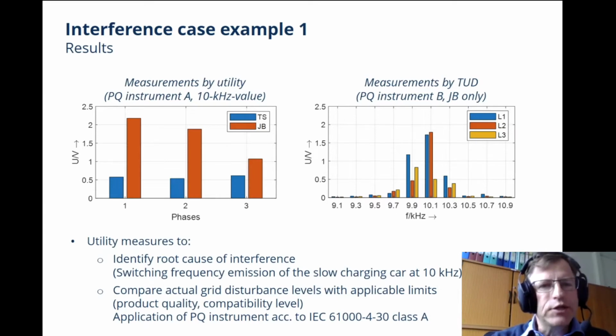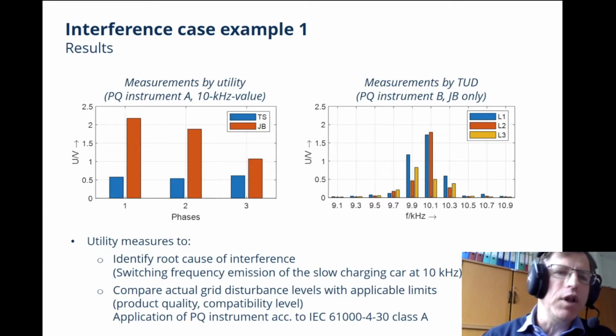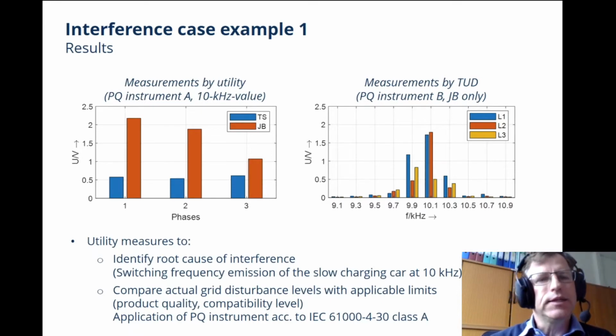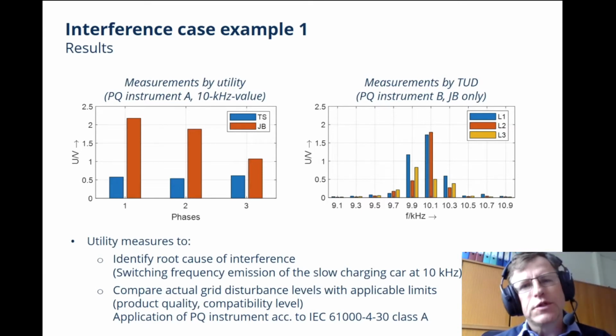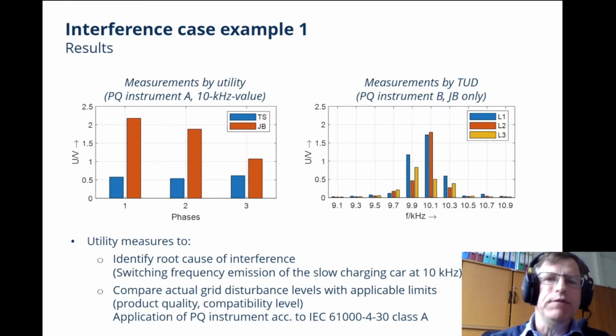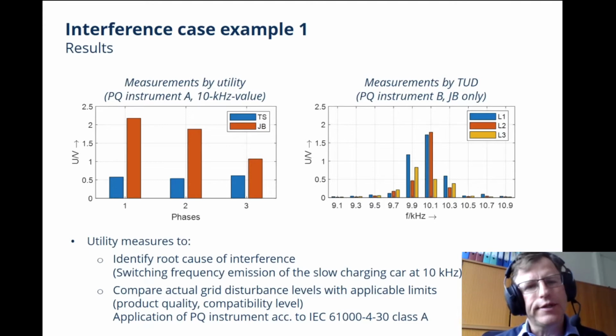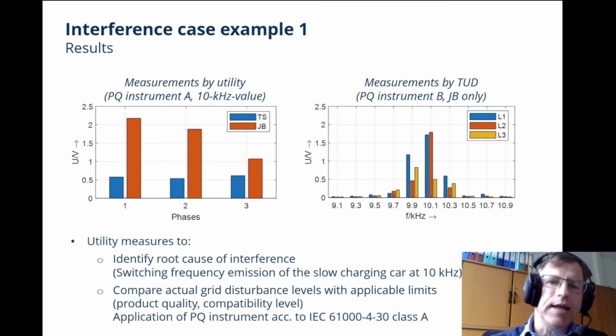What is quite interesting is that we measure at the transformer station only about 0.5 volts in each of the phases, while this is significantly amplified at the junction box 60 meters away downstream, up to a value of 2.3 volts. We also did some measurements in order to validate this, but we used a different instrument than the utility. This only shows the junction box measurement, but in a resolution of 200 Hertz bands, as defined or proposed in 61000-4-7. You can see now that at 10.1 kilohertz we have about 1.7 volts, which is lower than in the left figure, simply because there is a different frequency band.